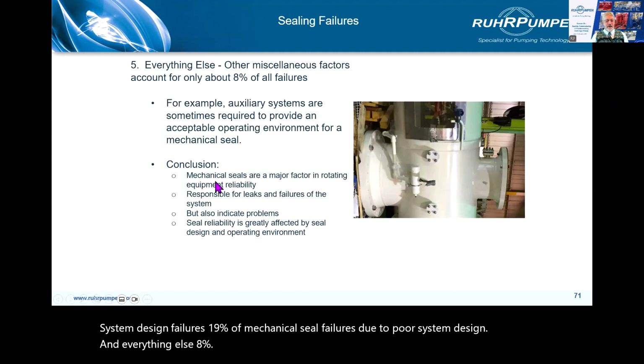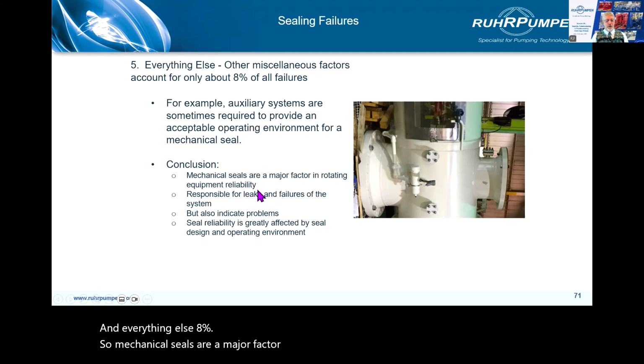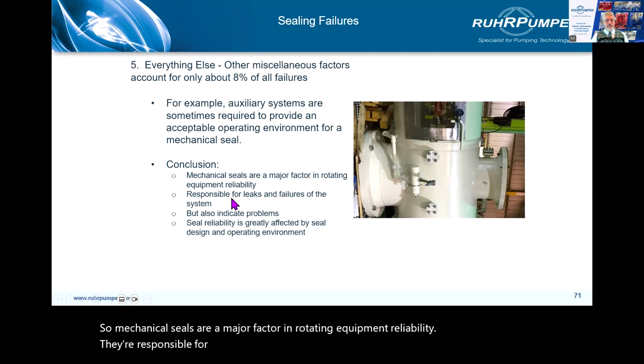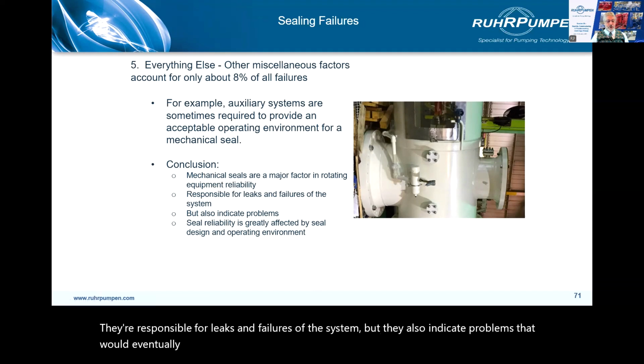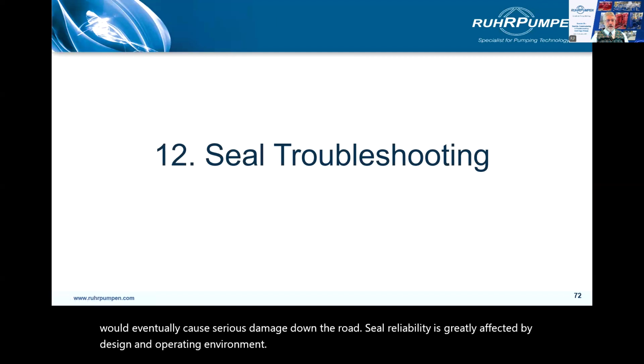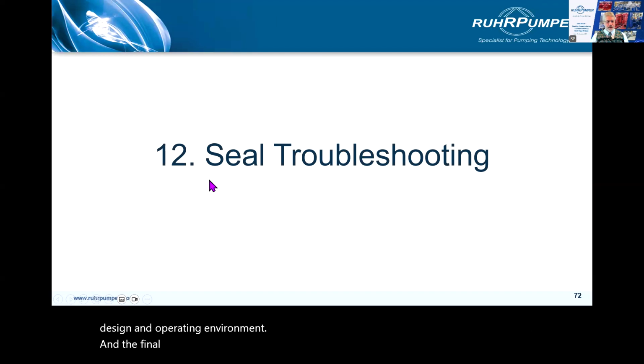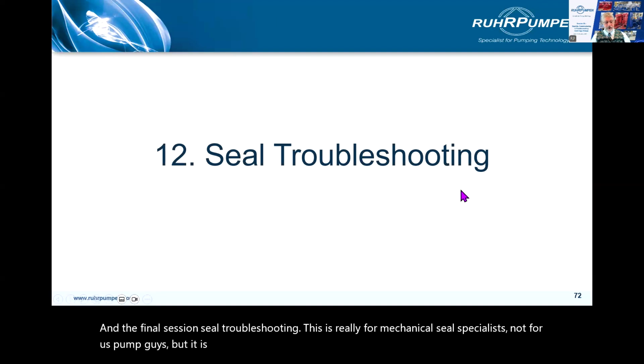So mechanical seals are a major factor in rotating equipment reliability. They're responsible for leaks and failures of the system, but they also indicate problems that would eventually cause serious damage down the road. Seal reliability is greatly affected by design and operating environment. And the final session, seal troubleshooting. This is really for mechanical seal specialists, not for us pump guys, but it is useful background reading.